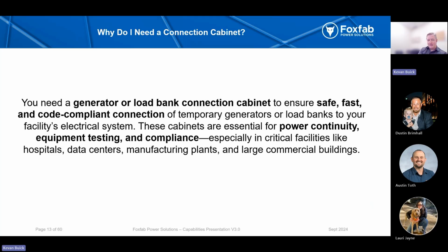Secondly, if you do have generators on site and want to load bank test them, having a proper load bank cabinet in place that may offer temp gen as well as load banking for your system will really reduce your overall cost of maintenance on your facility by allowing the load banking company to simply roll up their load bank and connect it, while pulling up a temporary generator if you need it. So there are many immediate and future benefits in setting up temp gen connection, load bank connection, or a combination of both within your facility.